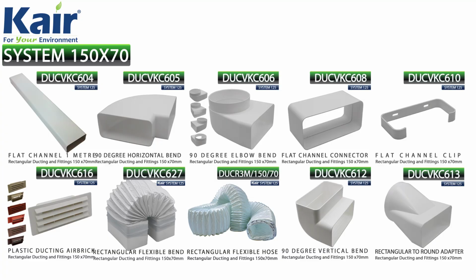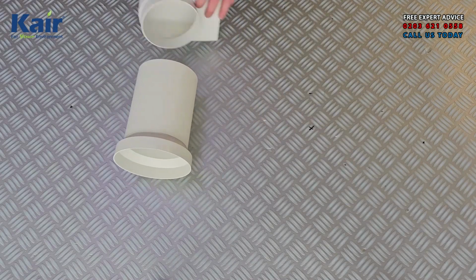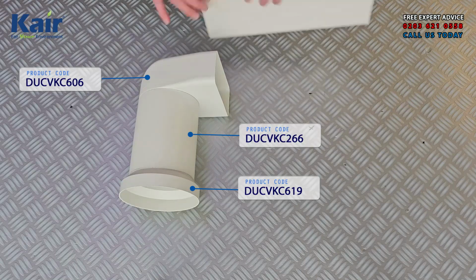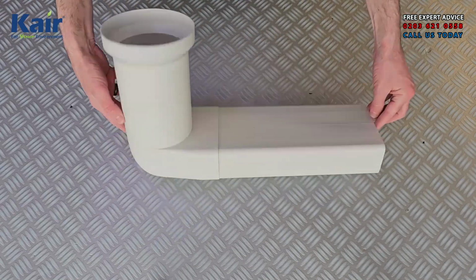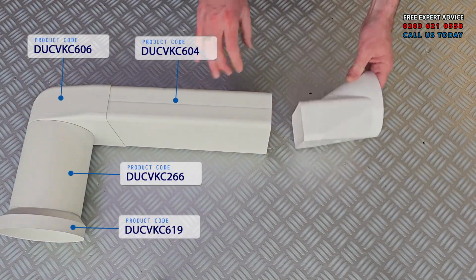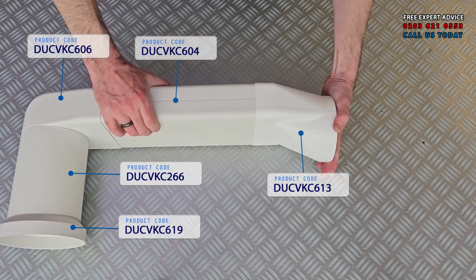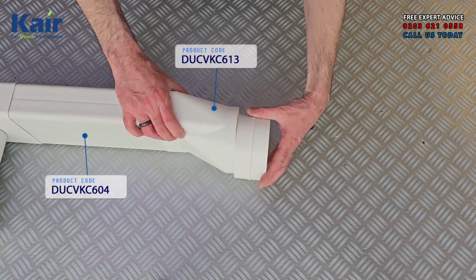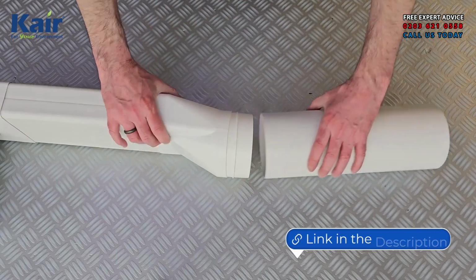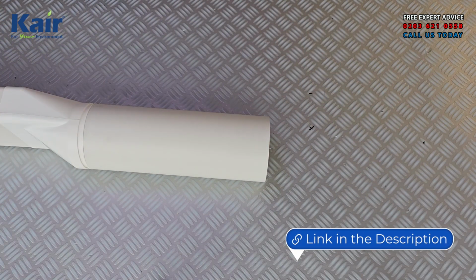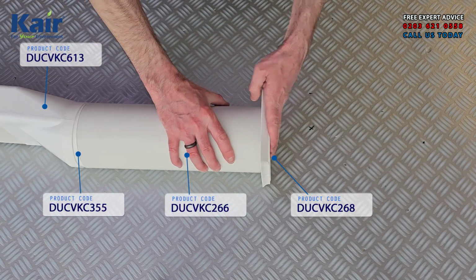The system includes standard components such as straight duct sections, connectors, bends and adapters, allowing complete duct runs to be created. A typical installation may run from the ventilation unit through 125mm round ducting, converting to 150x70mm flat channel ducting, and exiting through an external wall grille. Choosing the correct duct shape depends on the available space and installation layout.